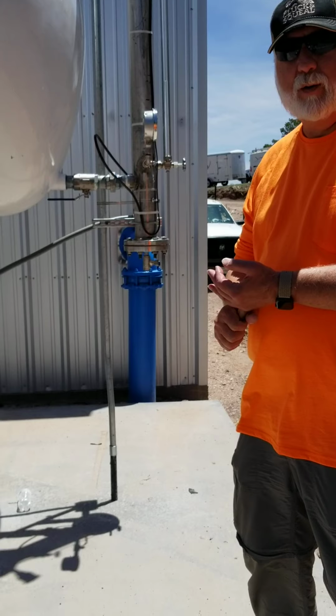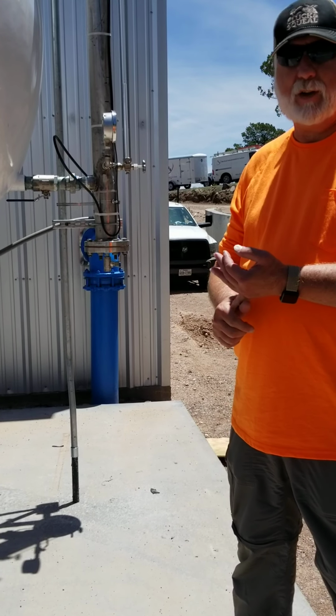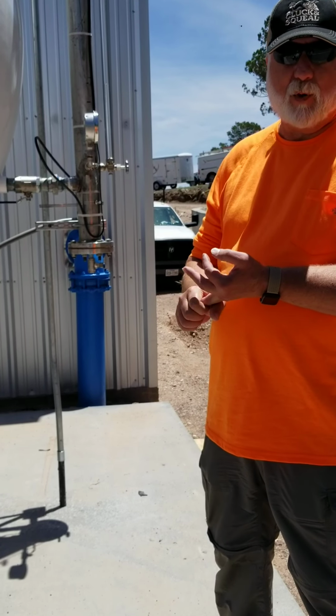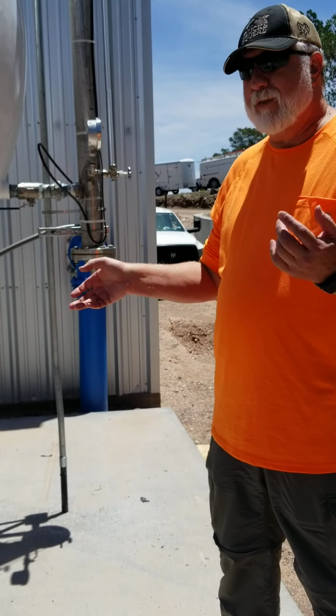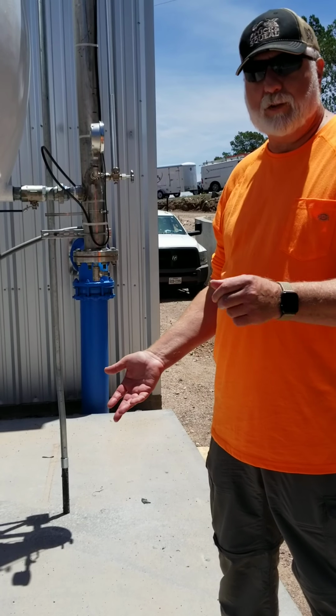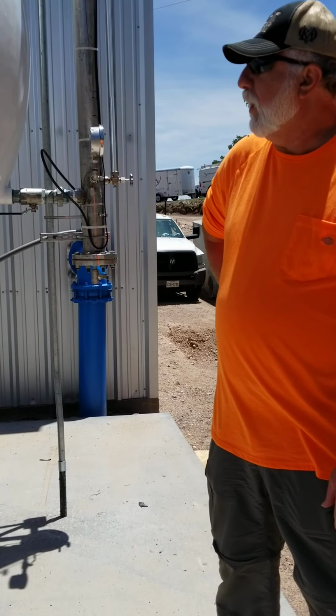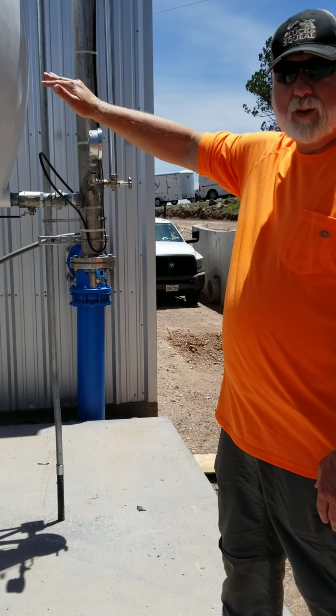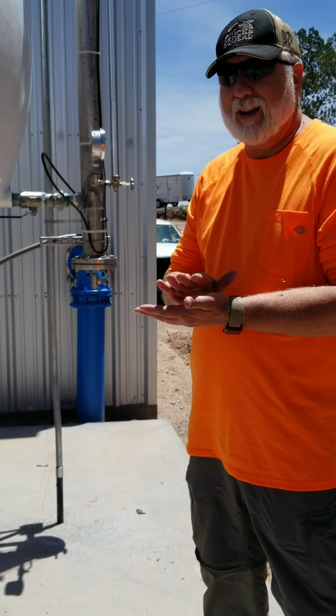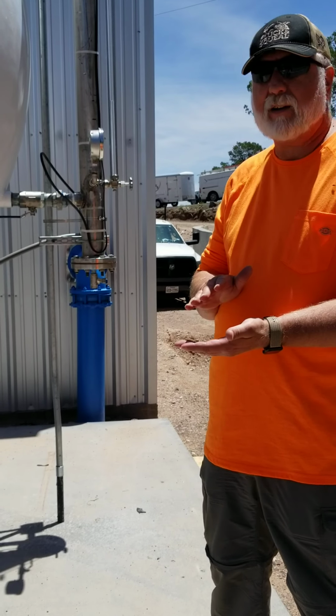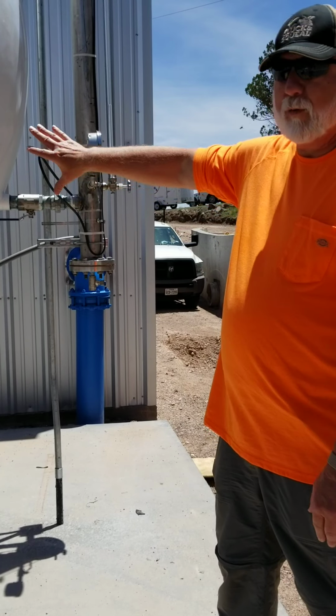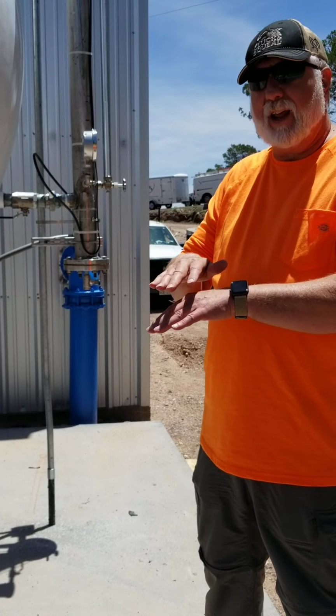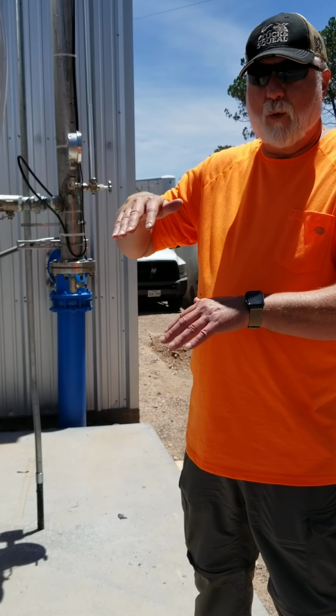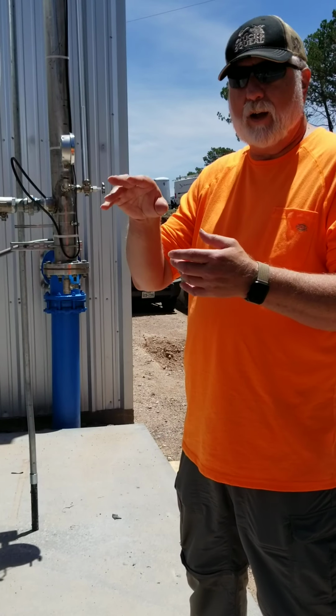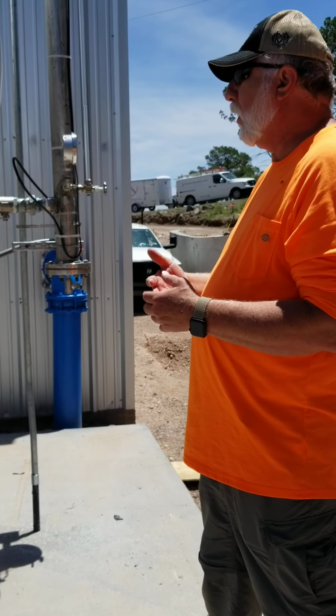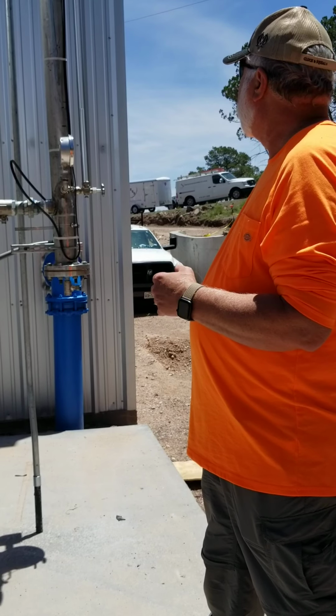The hydromatic tank is here for the sole purpose of regulating how often a pump turns on and off. And that is based on the fact that water does not compress. So if you had water in a pipeline and you opened a valve somewhere, the pressure would immediately drop to 0, and the pump would turn on. As soon as you close the valve, the pressure would spike up, and the pump would turn off. So to get around that, we have a tank that's partially filled with water, partially filled with air. The air is a compressible medium that we can calculate the rate at which it will expand and contract, which gives us a usable amount of water volume as water is used in the system. The water comes out of the tank, and that air expands to fill that void, and the rate at which it expands and the pressure decreases is calculable to determine how much usable water you have and how often the pump is going to turn on and off.